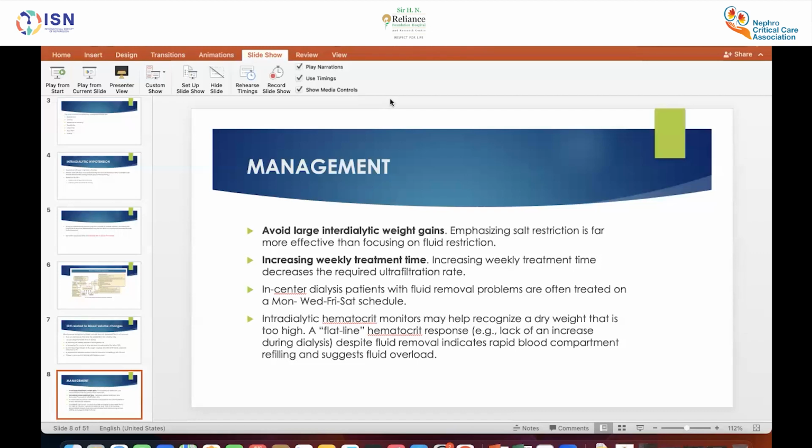So mid dialysis session, can we alter the ultrafiltration? Yes, it is second to second or minute to minute monitoring. So it is continuous monitoring. At any time frame you see that the crit line is going up, then you reduce the ultrafiltration.